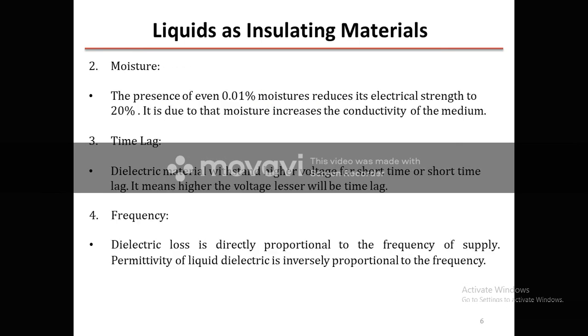The second point that affects the dielectric strength of a material is the moisture, as we have studied in the previous slide, that 0.01% of moisture reduces the dielectric strength by 20%. Okay, the third one is the time lag. Time lag is the time span taken by any insulator to completely break down. Okay, so the dielectric strength withstands higher voltage for a short time, or short time lag. It means the higher the voltage, the lesser the time lag, meaning it will take less time to break down.